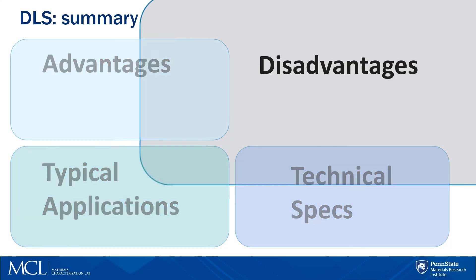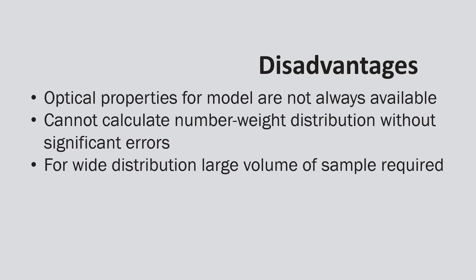Disadvantages include the fact that optical properties for the model are not always available, and we need to know the refractive index for the particles. Also, the instrument gives a volume-based distribution and we cannot calculate number-weighted distribution without significant error. For wide distributions, a large volume of sample is required.